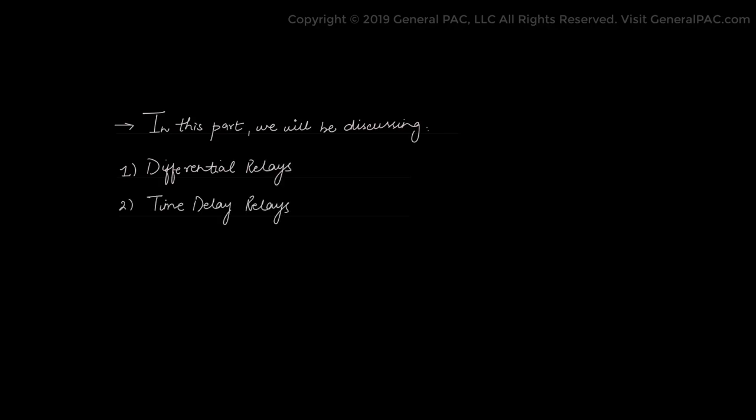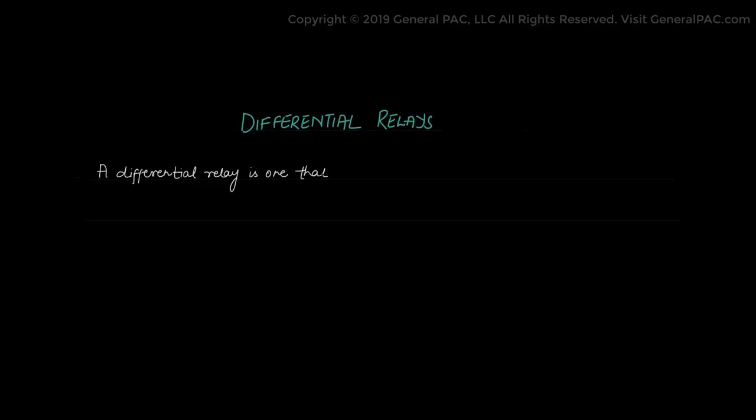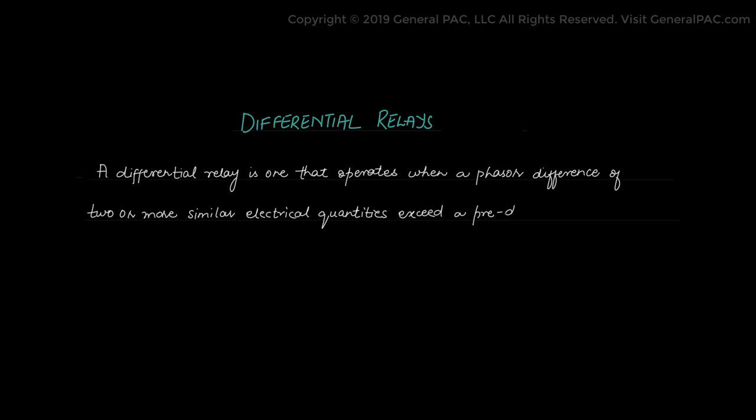The fifth type of relay we will be discussing is a differential relay. A differential relay is one that operates when the phasor difference of two or more similar electrical quantities exceeds a pre-determined value. The relay would operate a protective device or circuit breaker. When we say phasor, we are talking about a magnitude difference, an angle difference, or both — magnitude and angle — exceeding a set point of those two quantities.